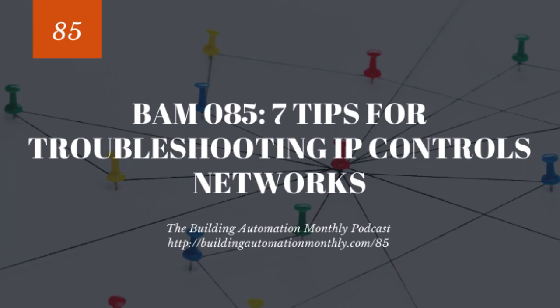And what that means is that certain traffic is going to be deemed more important by the switches than other traffic, and so the less important traffic goes into the trash can. Unfortunately, BAS manufacturers have not seemed to realize that they can tag their BAS traffic and make it a higher priority than other traffic. Otherwise, they would have done that, I would hope.